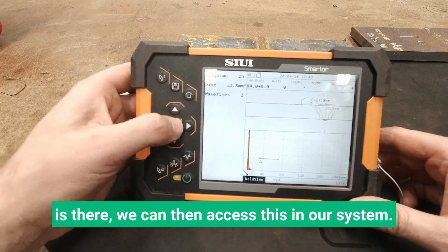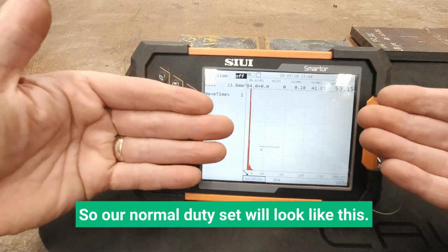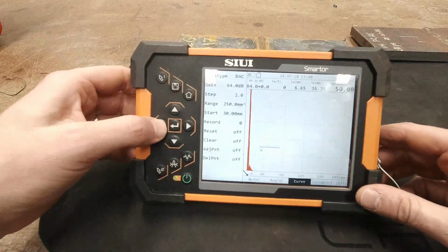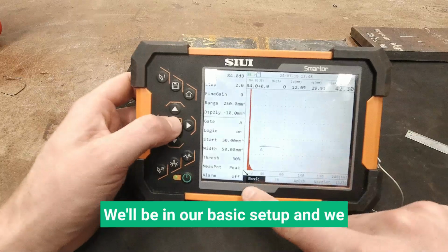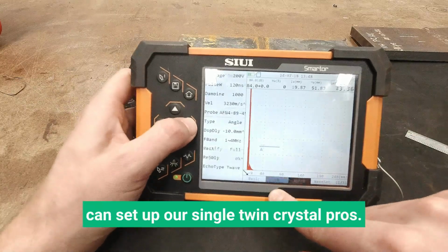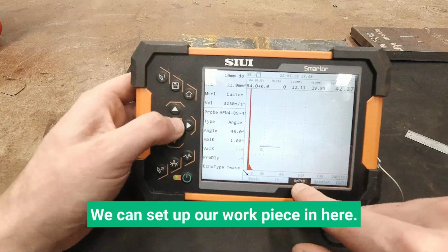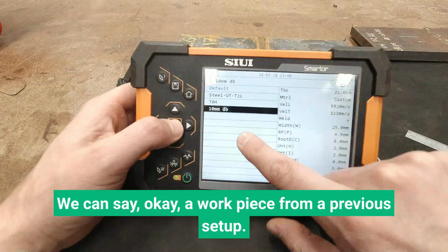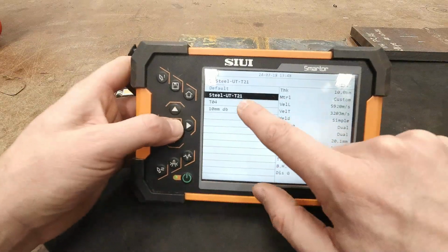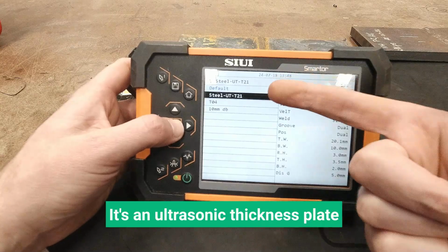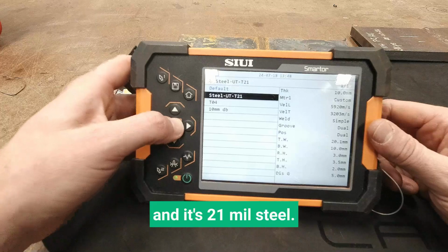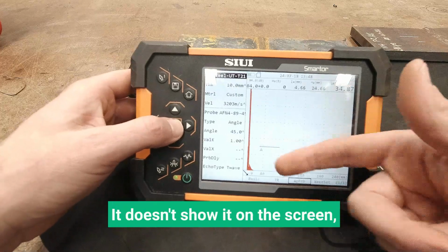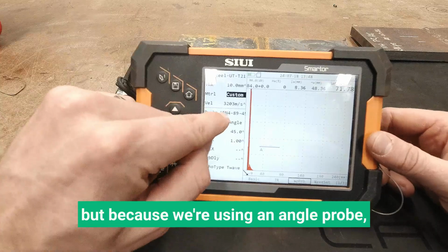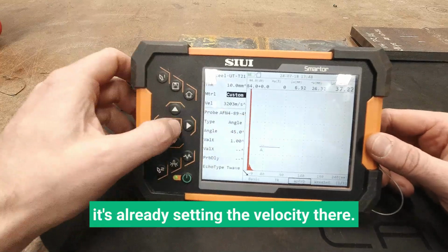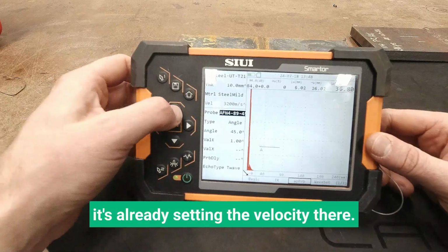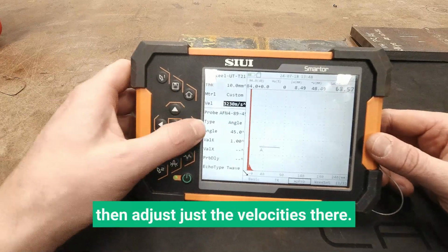this in our system. So our normal UT set will look like this. We'll be in our basic setup, and we can set up our single or twin crystal probes, we can set up our workpiece in here. We can say, okay, our workpiece from a previous setup, it's an ultrasonic thickness plate, and it's 21 mm steel. So that's our reference there. It doesn't show it on the screen, but because we're using an angle probe, it's already setting the velocity there, or we can do custom and then adjust the velocities there.